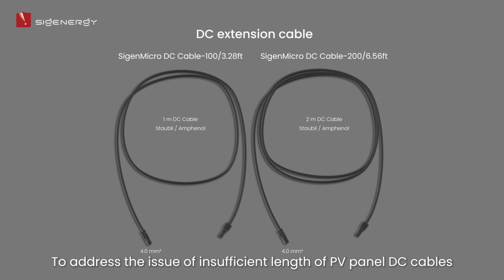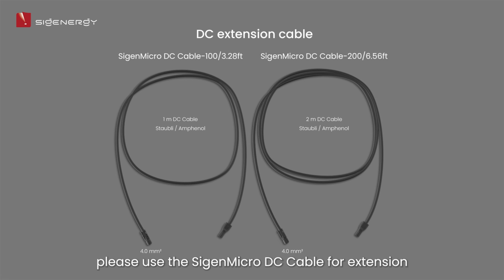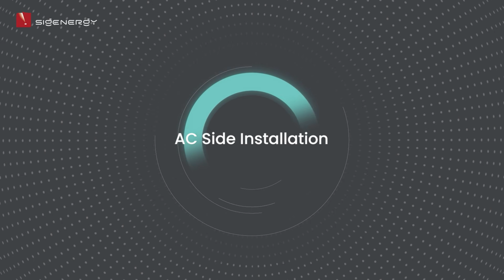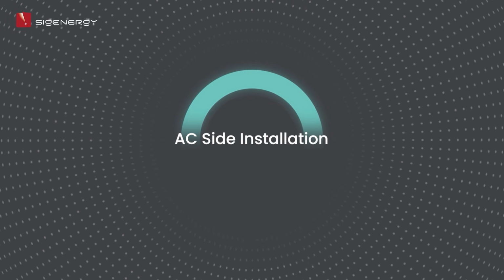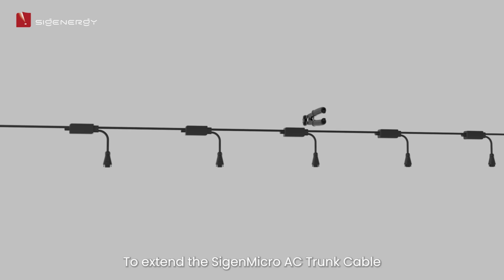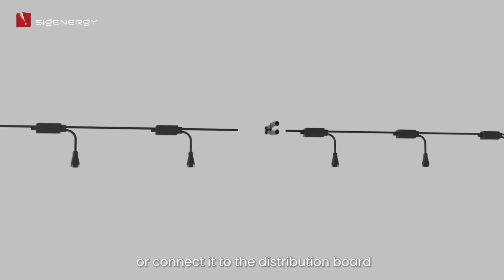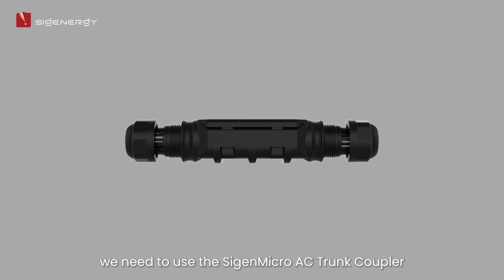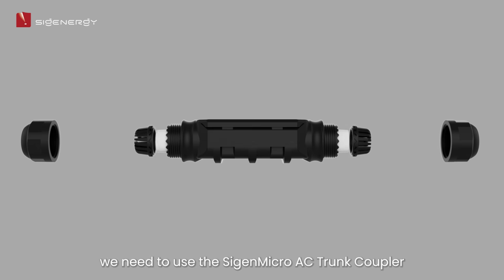To address the issue of insufficient length of PV panel DC cables, please use the SigenMicro DC cable for extension. It is available in 2 sizes, 1 meter and 2 meters. To extend the SigenMicro AC trunk cable or connect it to the distribution board, we need to use the SigenMicro AC trunk coupler.